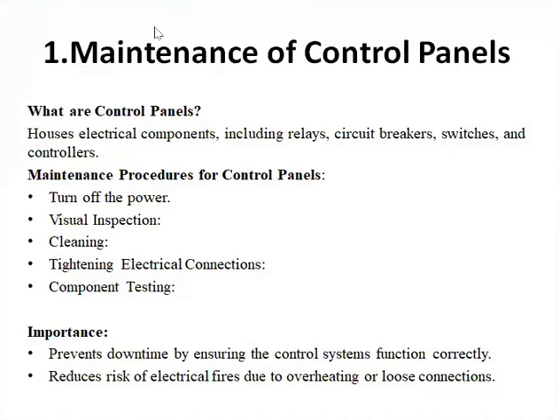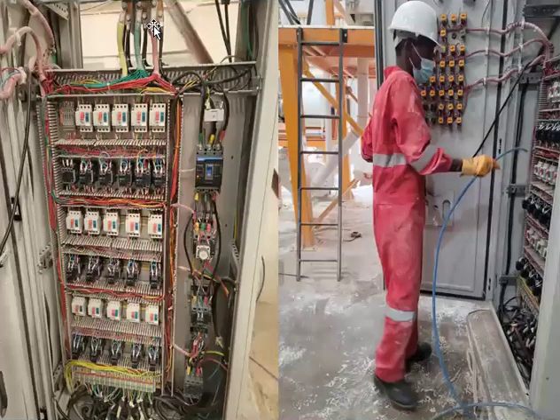First of all, these panels get some problems with the components that are inside. Any failure in a component can lead to something not working very well, either the motor not running or a control panel screen not coming on. So we have to make sure that the circuit breakers and the contactors are in place and working properly. Most times there are loose connections in this control panel.